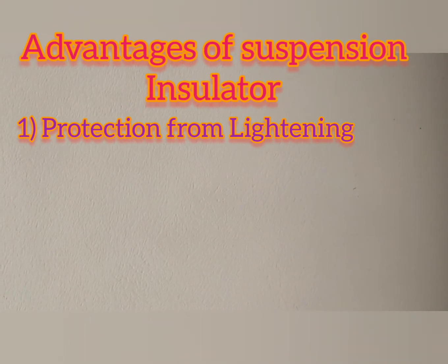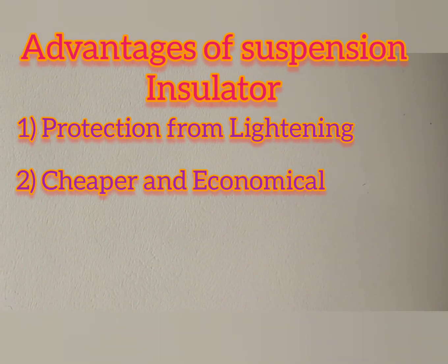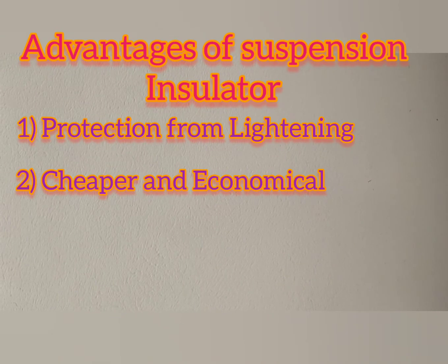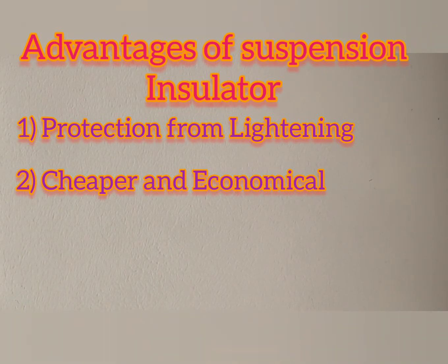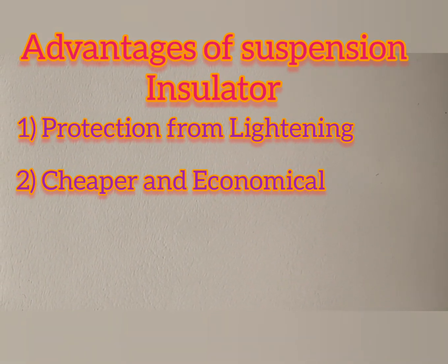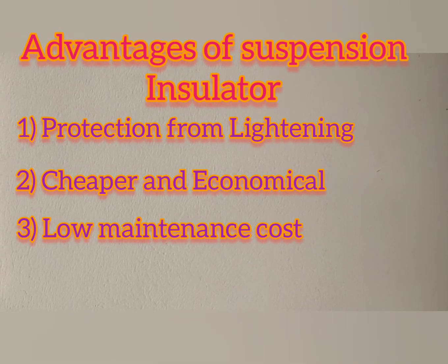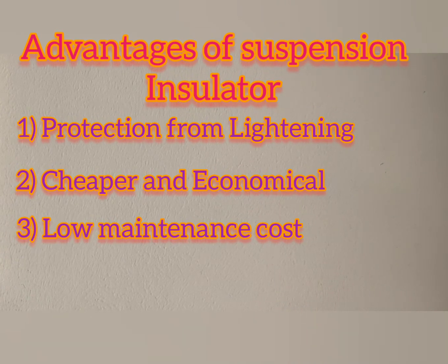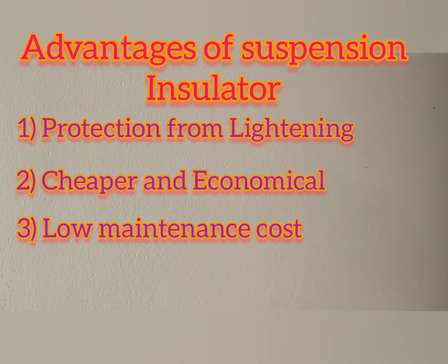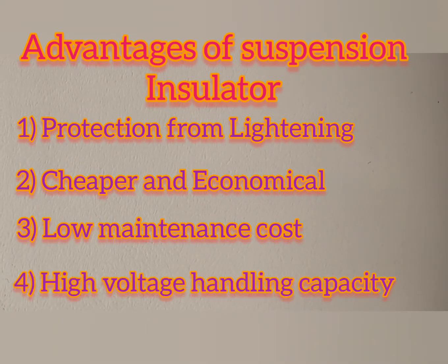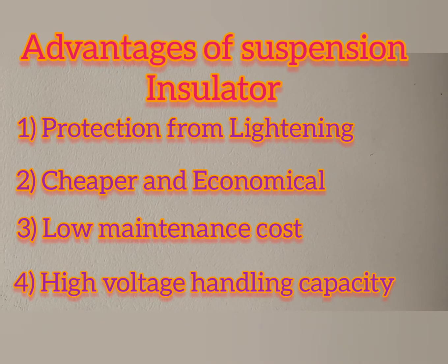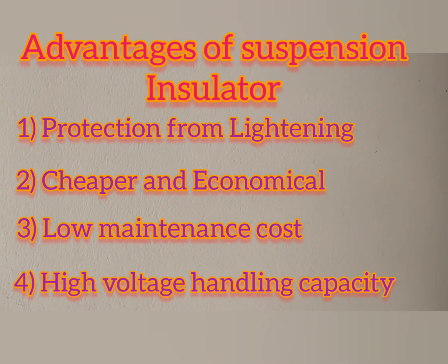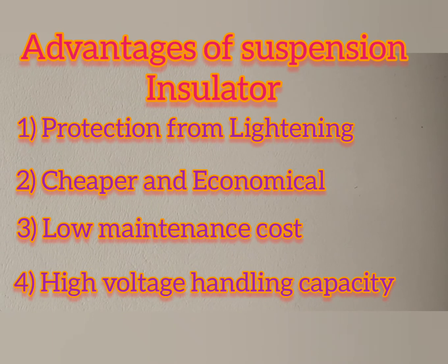Second advantage is suspension type insulators are cheaper and more economical than pin insulators for voltages beyond 33 kV. Next advantage is if any disc is damaged in a suspension string, it can be replaced easily. There is no need to change the whole string of suspension insulators. Each suspension disc is designed for 11 kV. We can increase the voltage handling capacity of these insulators by connecting a number of discs in series. In this way, system can be designed for any operating voltage.